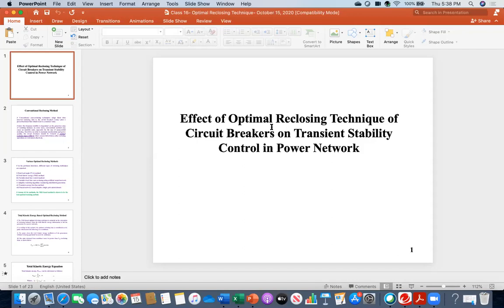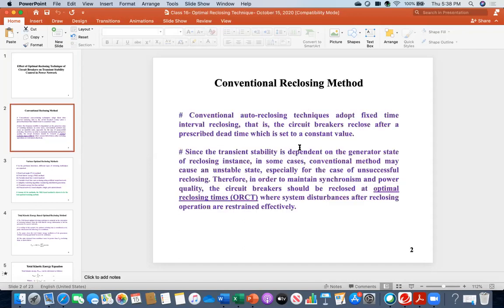But the optimal reclosing technique is not fixed. We will look at what that optimal reclosing technique is, and it has some benefits over the conventional technique. This is the conventional reclosing method - the conventional auto reclosing technique, where the reclosing system is automated. Both circuit breaker opening and reclosing are automated.